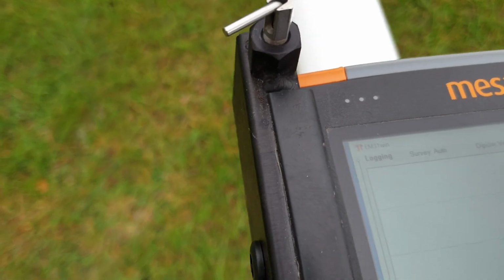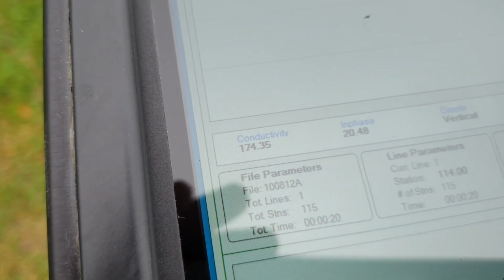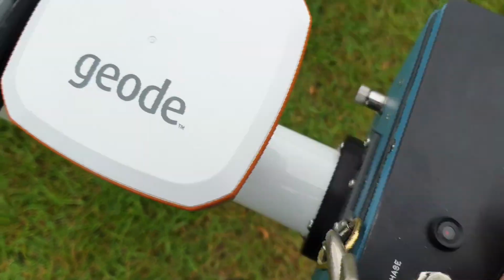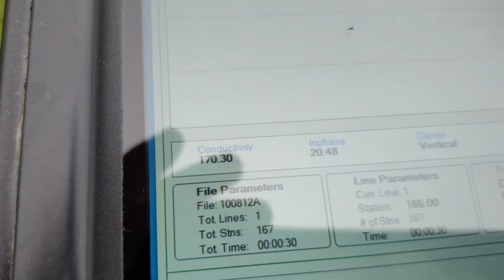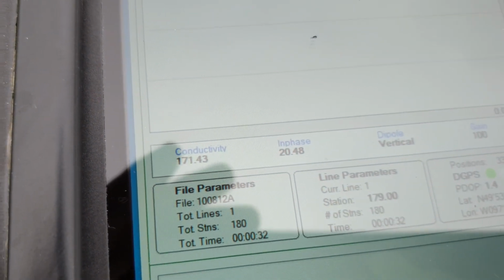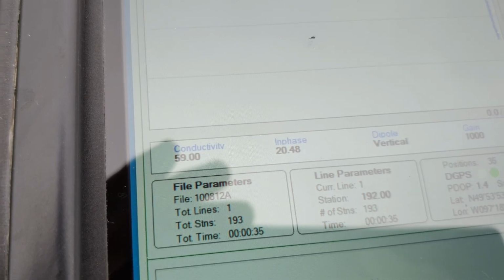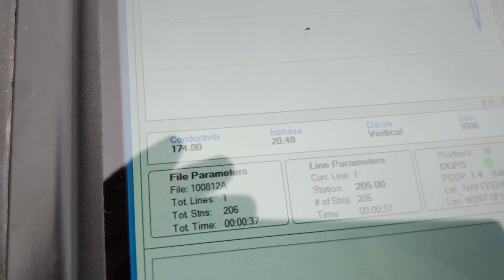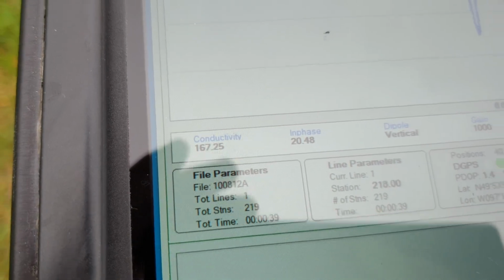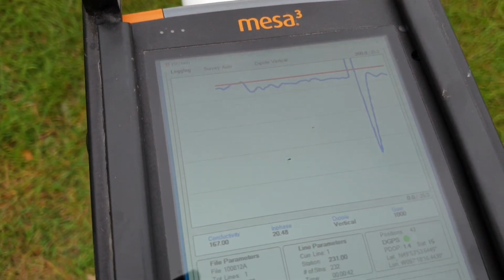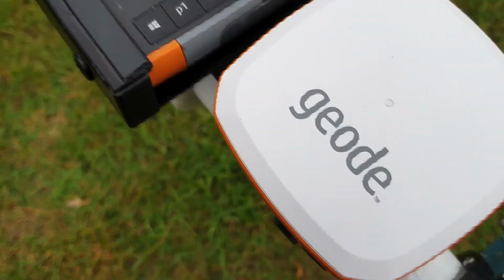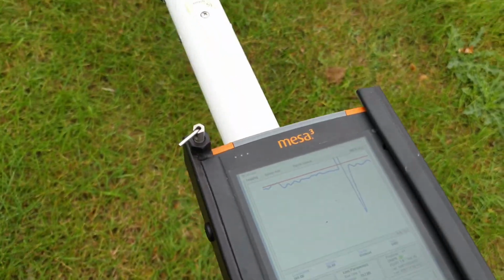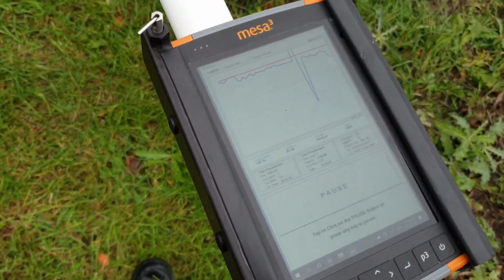If all of your data is up at the top of the screen, and your conductivity numbers are pretty high compared to the value on the switch, you should change the value of the switch. What happens is you'll lose a decimal point, but you'll gain, there you go, once it settles down, you'll gain some range. So now we're not going to overload the system because we went up to 1000. We were up at 175. So we can walk around.